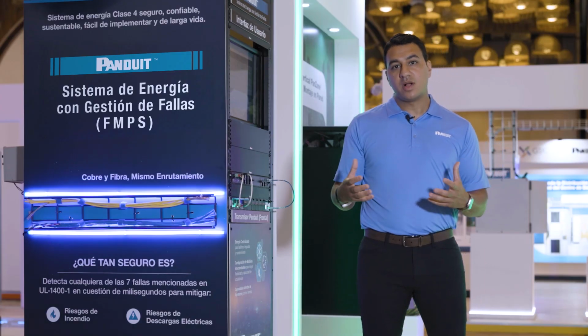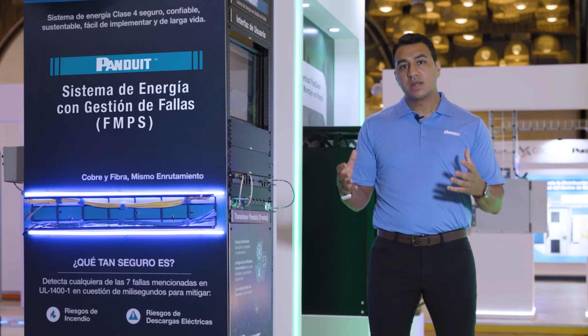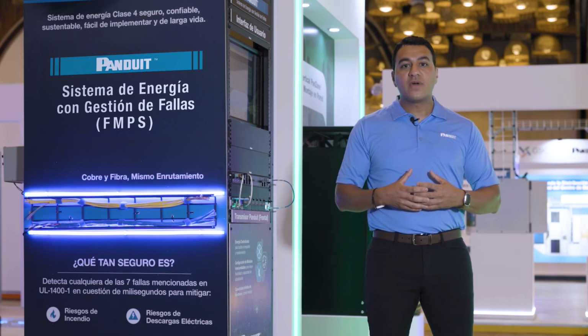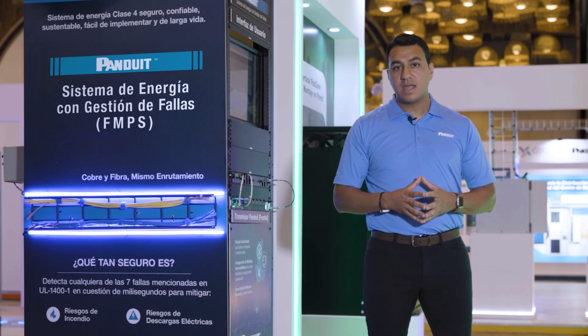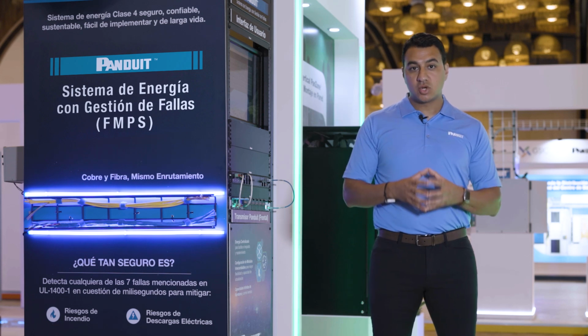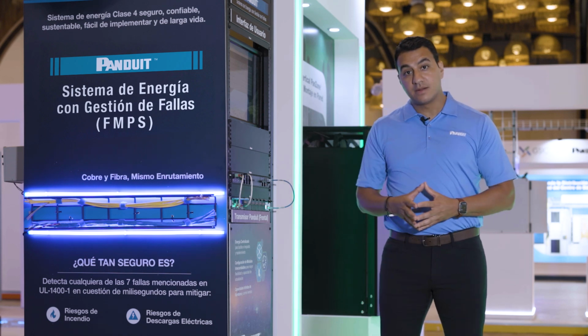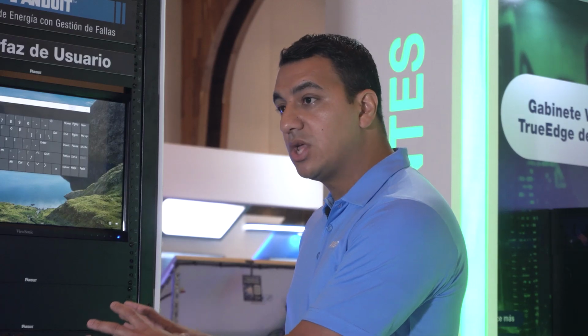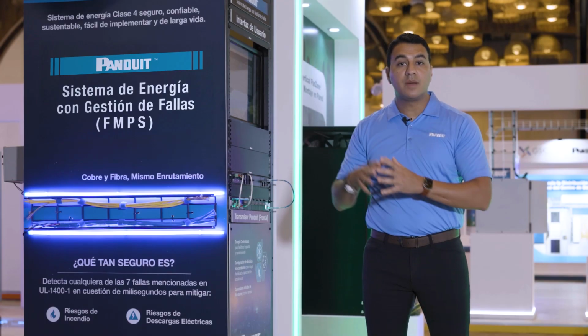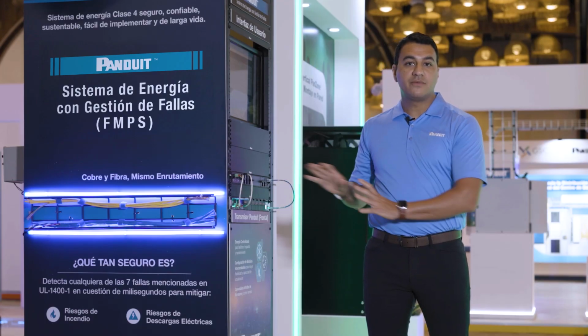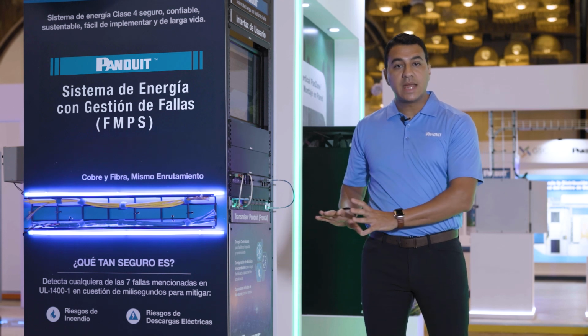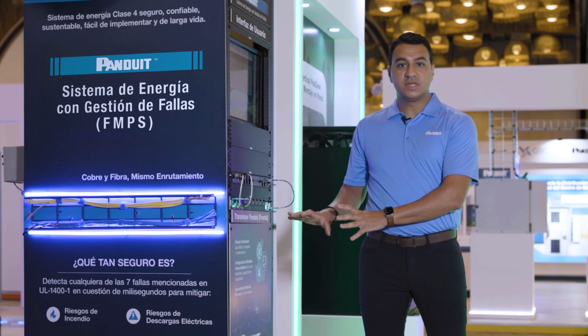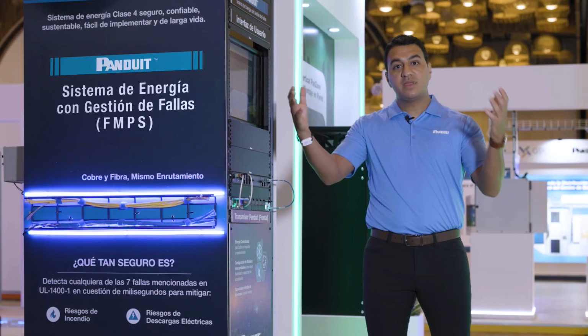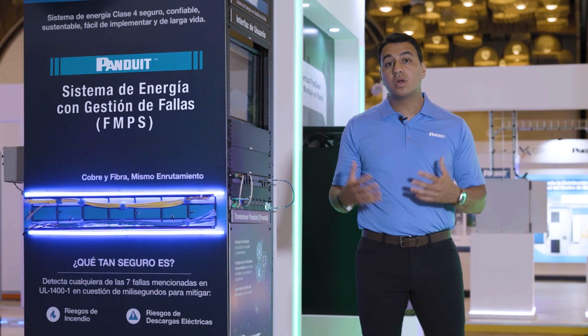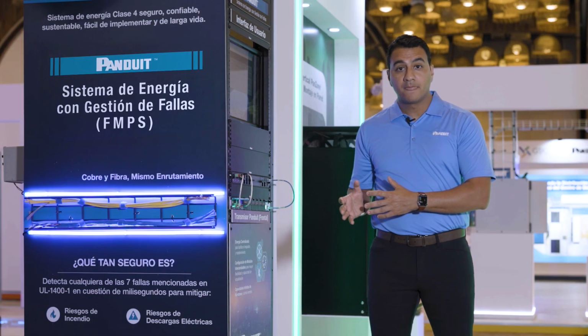The other great thing about Class 4 now is, think about it, because you can provide power up to 2 kilometers away, you're providing power from one central location, like where we are here. So one centralized location of power, sending power 2 kilometers away, gives you now the benefit of centralizing, meaning you can now centrally back up your system with a UPS. And now every device that's up to 2 kilometers away from the source is backed up.